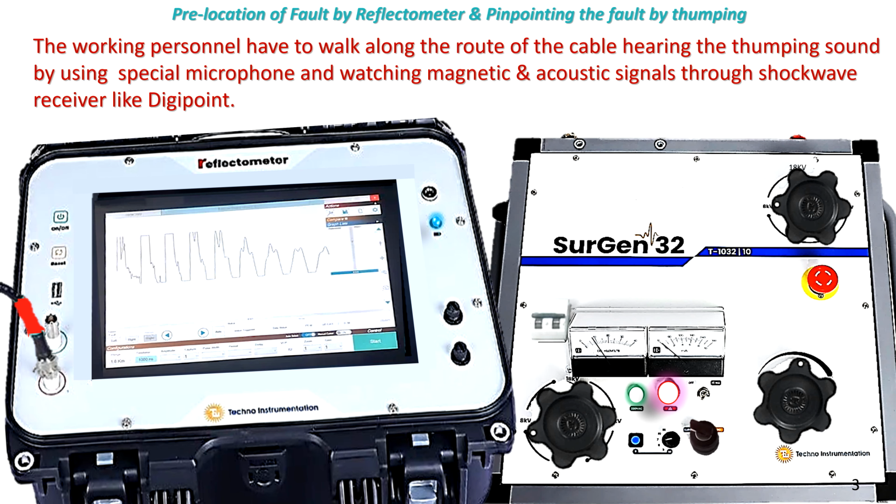The working personnel have to walk along the route of the cable, hearing the thumping sound by using a special microphone and watching magnetic and acoustic signals through a shock wave receiver like DigiPoint.